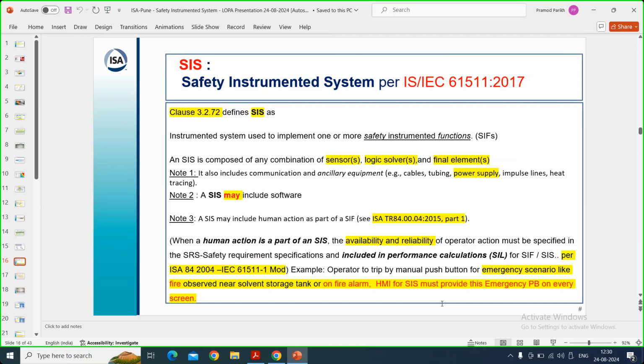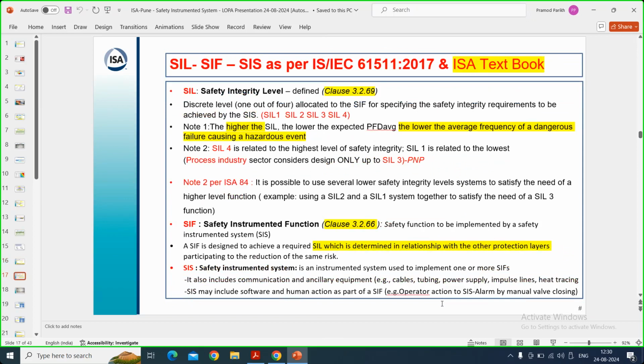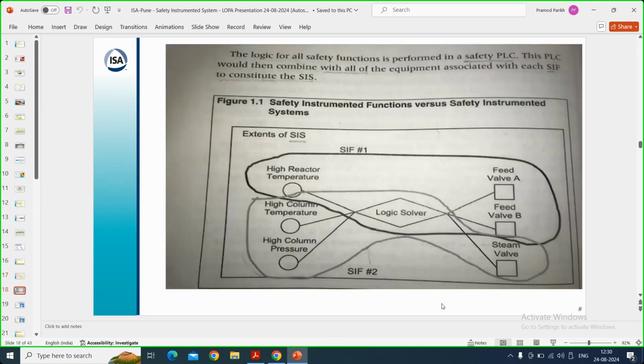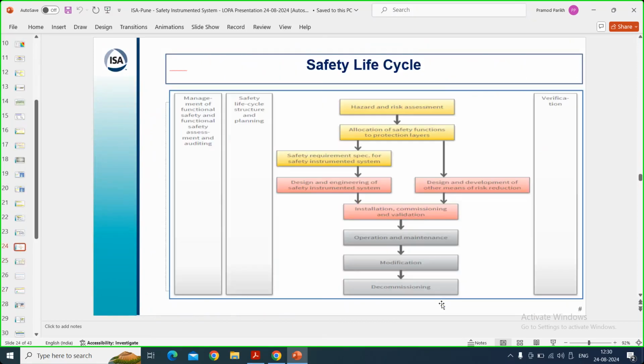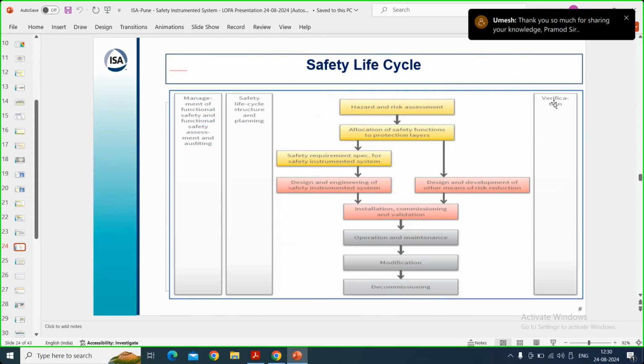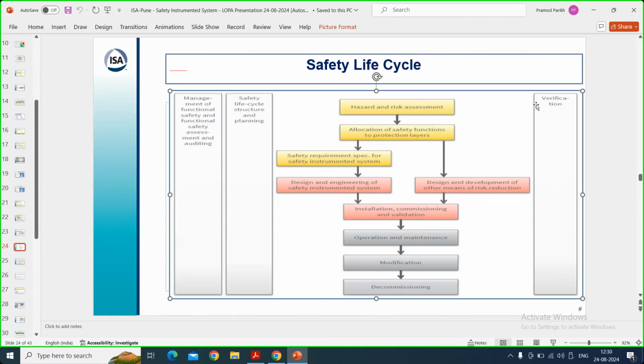Sir, what is the difference between SIL verification and validation? Yes, SIL validation, because I'll show you the slide. Unfortunately, I could not go through it. See, in this slide, verification, can you see my slide? Yes, sir. Verification is applicable all throughout the safety life cycle. You can see this block. So at every stage you verify: you verify hazard and risk assessment, whether it is done properly or not. You verify whether allocation of safety function is done properly or not. You verify whether you have designed the system properly or not. So verification is applicable to each and every phase of the safety life cycle. Whereas validation, you can see here, installation, commissioning, and validation.